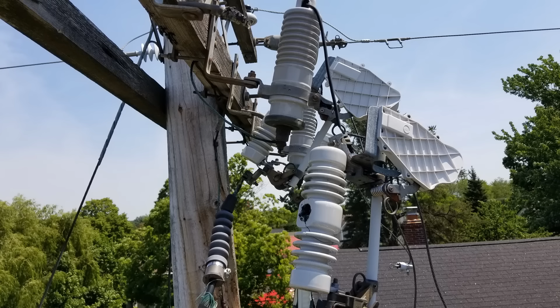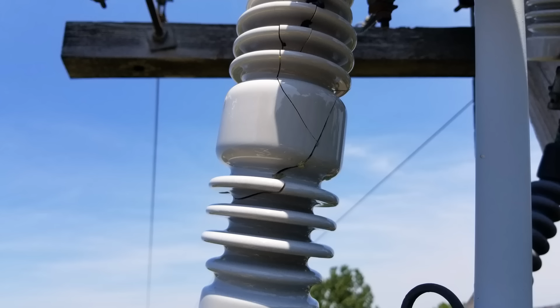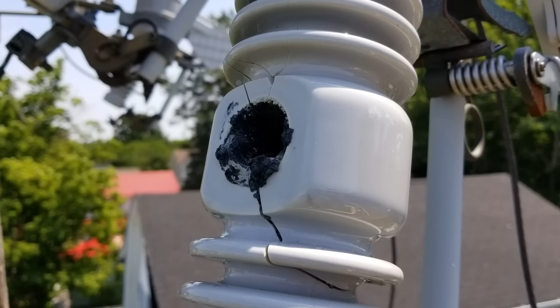This shot here is from July 5th, 2018, just a couple pics of a broken cutout. The reason I wanted to show these in one of my most recent videos was showing the cracked bell type insulators. A viewer had asked if the ring test works on cutouts, and I mentioned that it doesn't. One indicator is if you look on the back where it attaches to the bracket on the pole, oftentimes the grout will start turning black and bubbling out before the cutout fails. In these pics you can see that quite clearly. This is a pretty extreme case of a broken cutout, you could see it right from the ground. But sometimes you'll see the grout boiling out in a cutout without seeing any cracks at all, and that's a good visual indicator that the porcelain's been compromised.